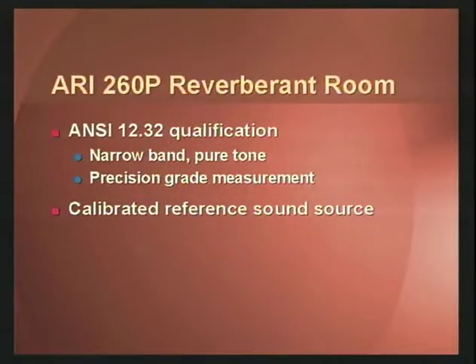ARI-260P also requires that the reverberant room that we're using for the testing is qualified beyond the normal requirements, and we use an ANSI 12.32 qualification. This qualification is narrowband in nature and takes into account pure tones within the sound spectrum. This is a precision grade measurement. It also employs into ARI-260P the concept of a calibrated reference sound source so that the data that we get from the reverberant room is very accurate. This calibrated reference sound source, the qualified reverberant room, and the ducted technique, combined with stringent requirements as to how we test this mapped concept, gives us a very accurate database.